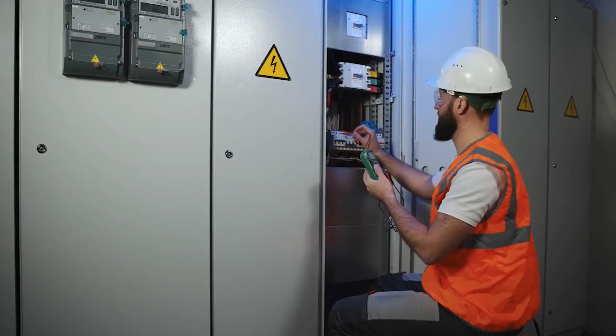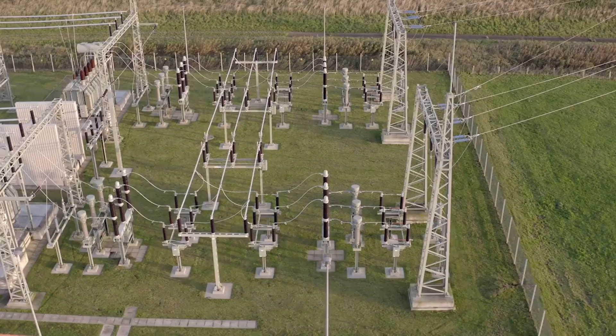Let's break down the 3 most critical components of any SCADA system, the parts that physically connect machines to operators. RTUs, remote terminal units. RTUs are used to collect data from field instruments in remote locations. They gather sensor readings like pressure, flow, and temperature, and transmit them back to the central control system. They are often ruggedized to survive harsh environments and can operate on low power in isolated areas, like offshore oil rigs or mountaintop weather stations.